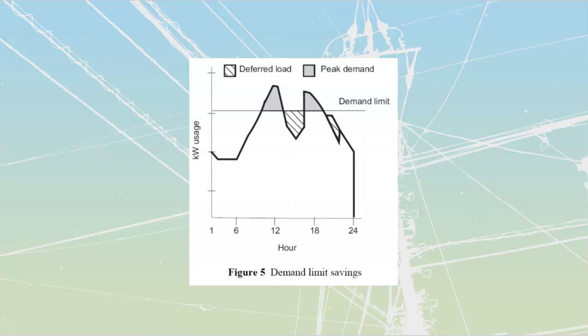So what we will do is we need to monitor and watch that, because in a lot of cases you're going to have a demand limit. BC Hydro will sell you as much power as you need, provided it doesn't screw over their system. But in a lot of cases, what they have going into your facility is a single transformer that's feeding a bunch of others. And they have to balance all that.